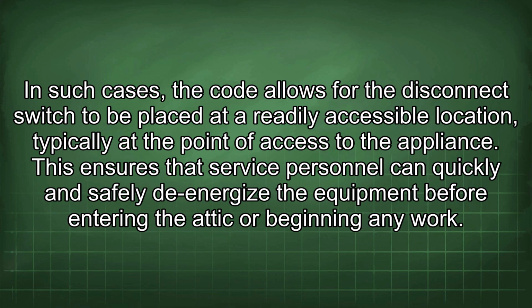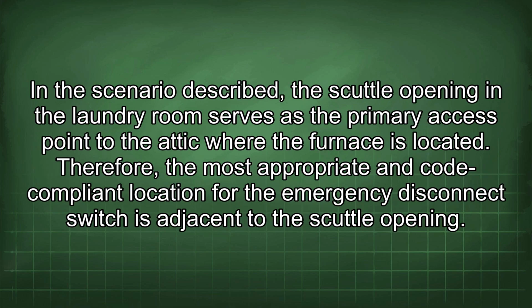In such cases, the code allows for the disconnect switch to be placed at a readily accessible location, typically at the point of access to the appliance. This ensures that service personnel can quickly and safely de-energize the equipment before entering the attic or beginning any work. In the scenario described, the scuttle opening in the laundry room serves as the primary access point to the attic where the furnace is located. Therefore, the most appropriate and code-compliant location for the emergency disconnect switch is adjacent to the scuttle opening.